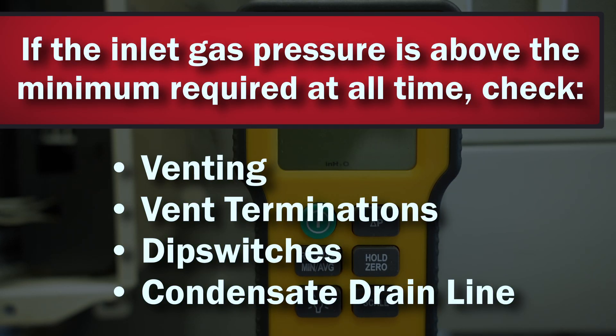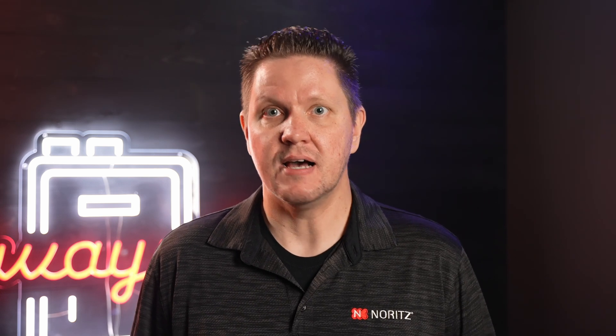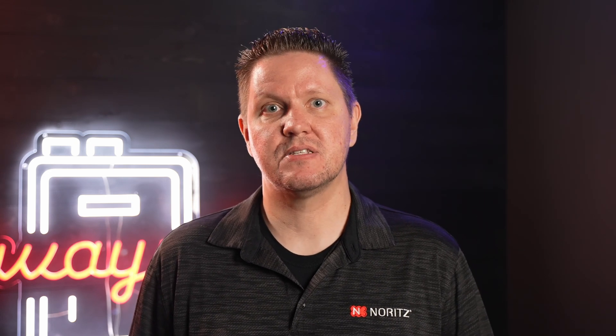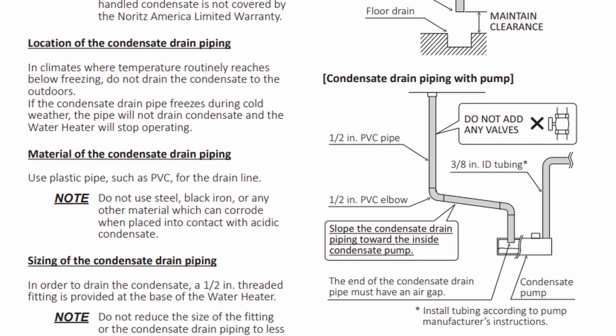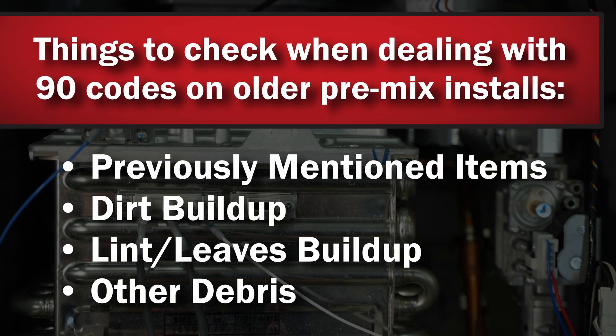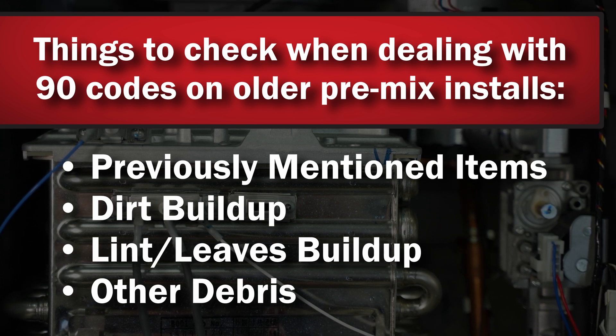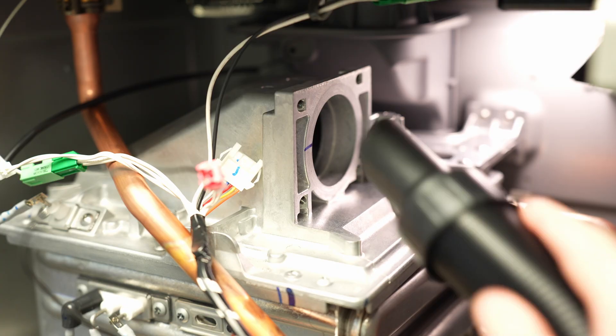If the inlet gas pressures are above the minimum required at all times, you're likely looking at an issue with the venting, termination, dip switches, or condensate drain line. Make sure the guidelines in the installation manual regarding venting limitations are followed. Assuming they are, also make sure you've correctly set the dip switches according to how it's vented. Check that the intake and exhaust terminations are done with approved terminations. Also make sure the condensate drain line under the unit is the correct size, routed properly according to the guidelines in the manual, and that the end of the drain line is not submerged in water. For existing older installations of pre-mix units, you're still going to check all of the previously mentioned items, but you're mostly looking for a buildup of dirt, lint, leaves, or other debris that have obstructed the venting. Clean any debris from terminations and make sure the condensate drain line is still free of any obstructions. If cleaning those items does not resolve the 90 code, a deeper cleaning of the fan and burner may need to be done by a professional.